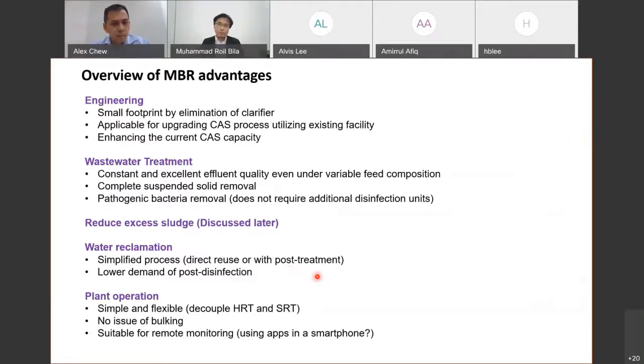In terms of plant operation, MBR is simple and flexible. I don't know if this term is familiar, but we can decouple what we call solid retention time and hydraulic retention time, which is otherwise very difficult to do in conventional activated sludge. We have no problem with sludge bulking. In fact, there are many reports indicating that sludge bulking is better in enhancing the effluent quality when it happens in MBR, and it is suitable for remote monitoring.